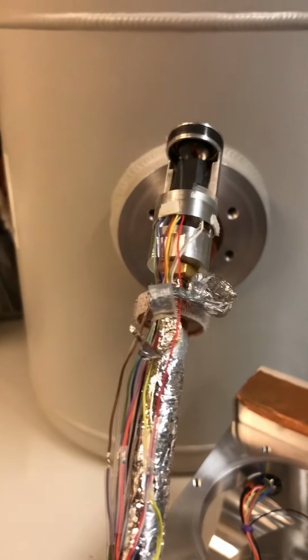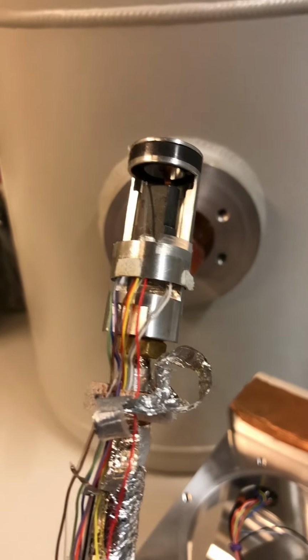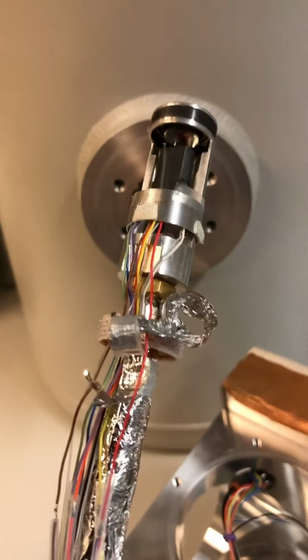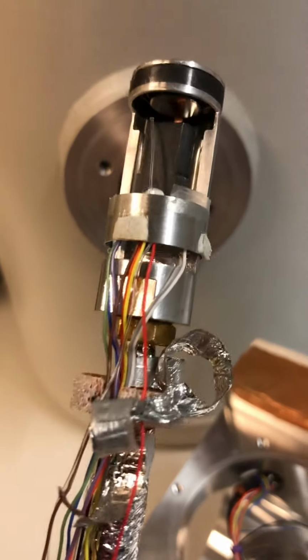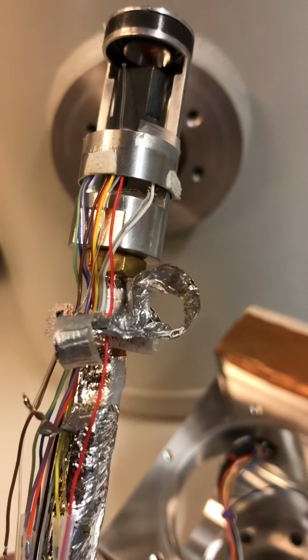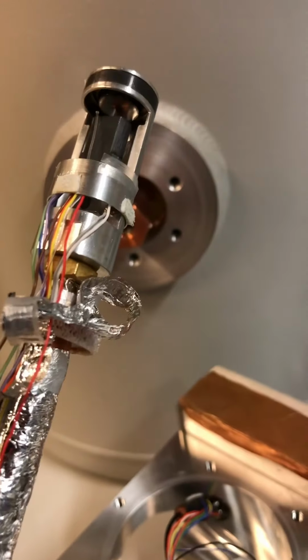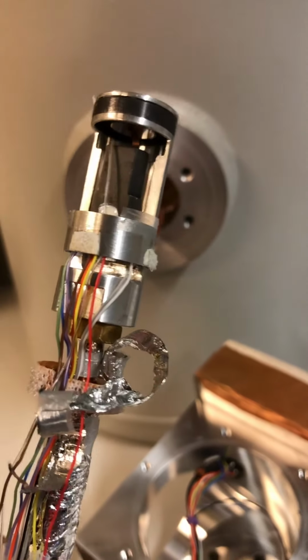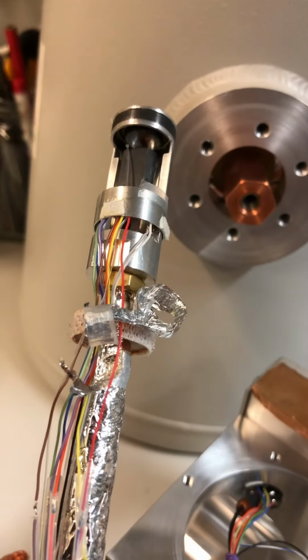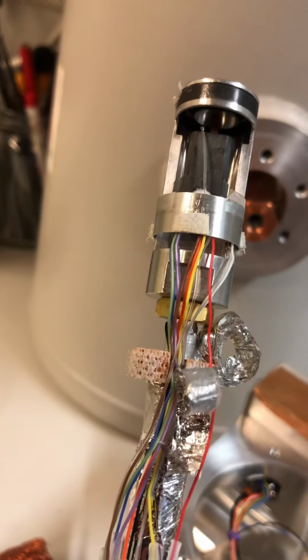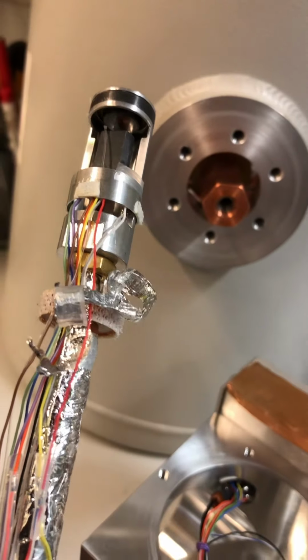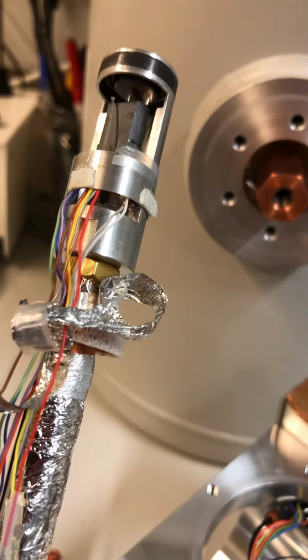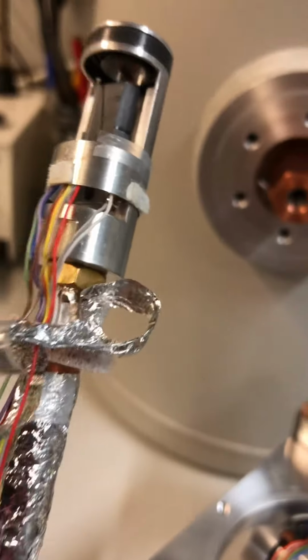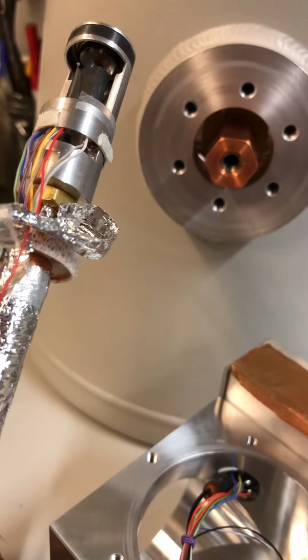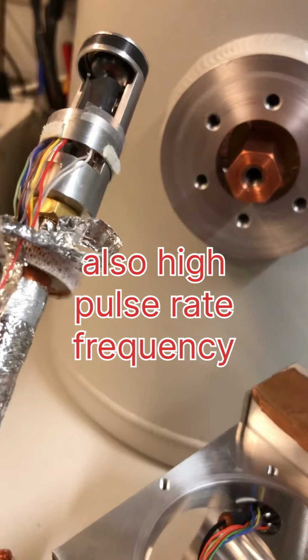Around the detector is earth, aluminum, and plastic insulator. And then electrons go to the center of the detector, where they are collected. High voltage DC is necessary to create a large PN junction, where it has a small capacitance, and small capacitance means that one can charge it up with a small charge and detect small energy X-rays with good resolution.